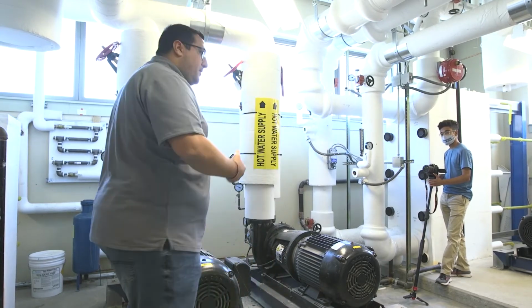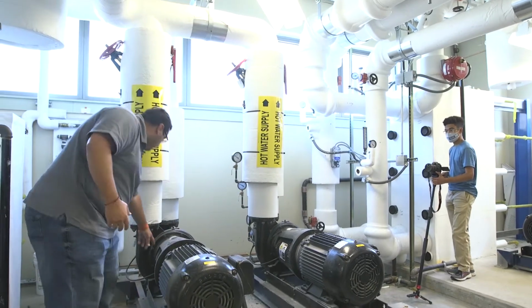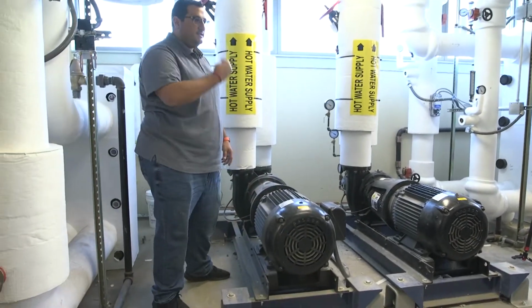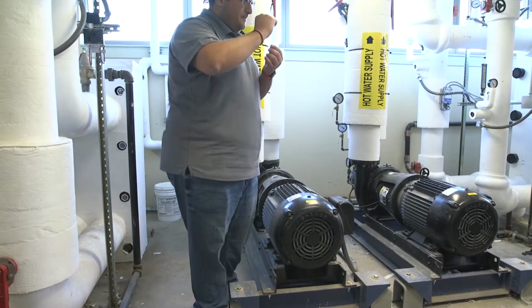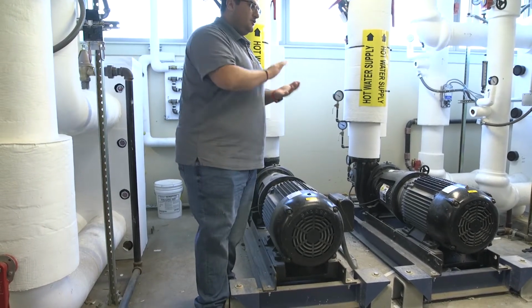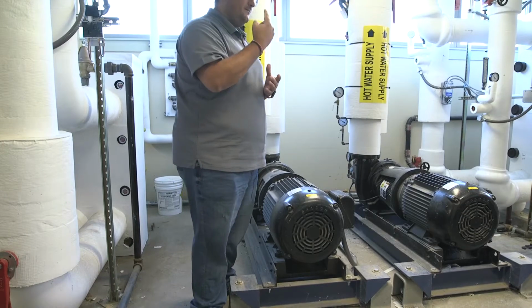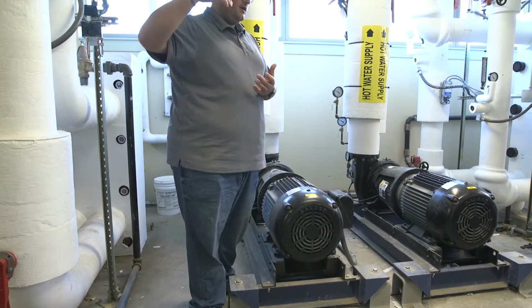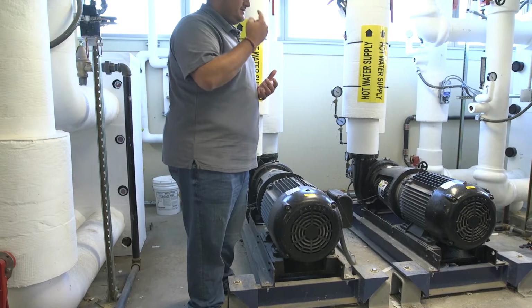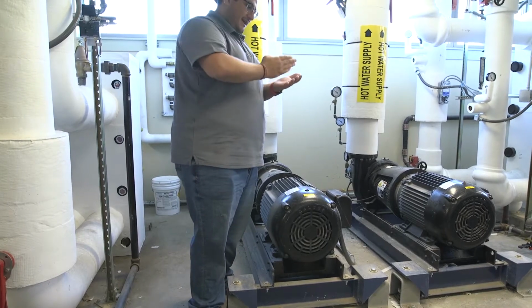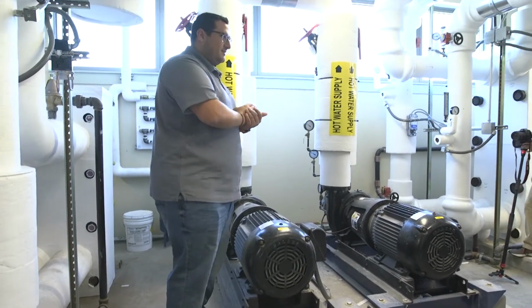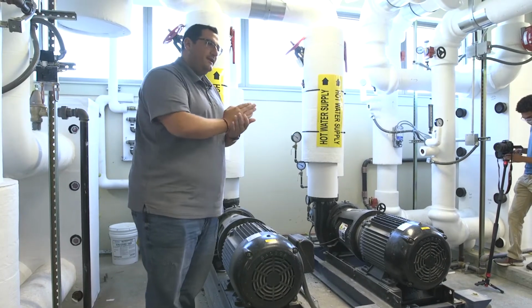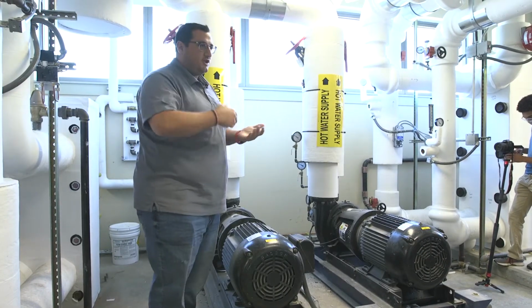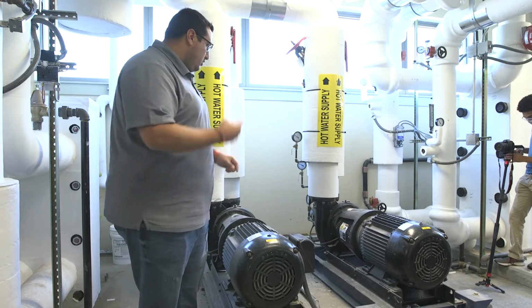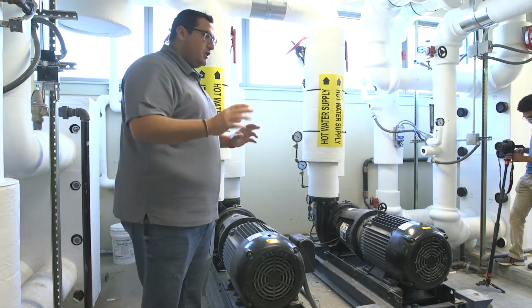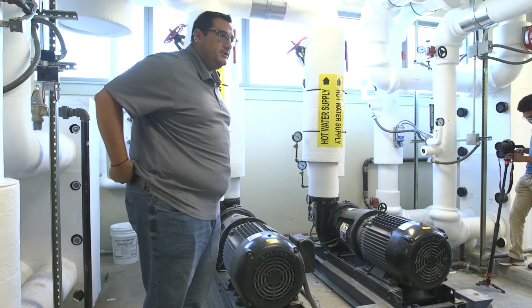If the pump seal leaks, you're going to see it over here towards the shaft. Once you see a first drop, you know you have a problem. That's when you've got to get somebody in to repair it, because that first drop will become much bigger in the near future. It only takes one hair on your head cut into 10 pieces to scratch the seal face, and that's enough for water to start making its way through. Once water comes in, it starts to erode everything else and makes it worse. So once you see one drop of water come out of this, for the most part you have a seal leak, so get somebody in here to replace your seal.